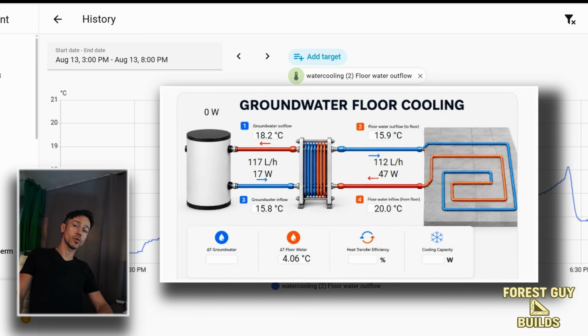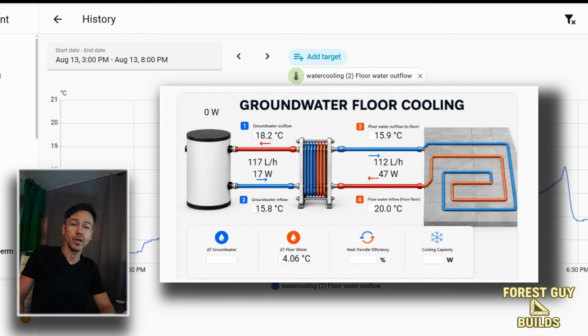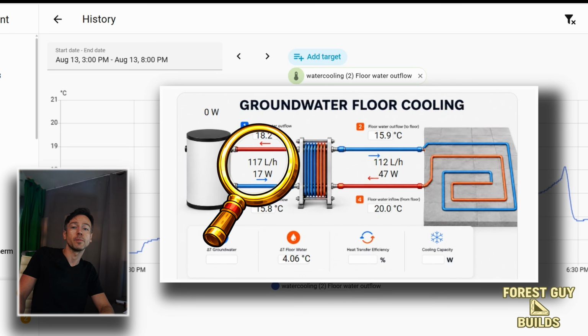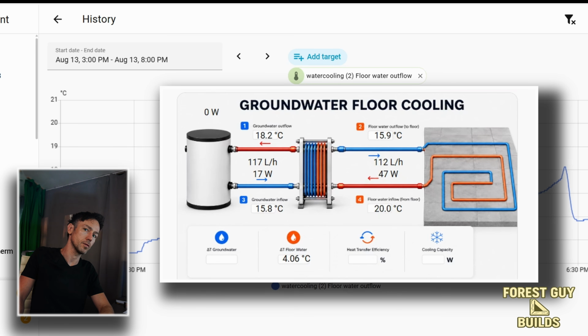Besides this, you saw the flow rates. Both the groundwater side and the floor circuits are running around 100 liters an hour, giving us a delta of around 5 degrees. As someone mentioned in the comments on a previous video, a delta of around 5 degrees is quite normal behavior for the type of heat exchanger I'm using here, so that lines up well having roughly the same flow on both sides. The bigger delta of around 7 degrees I had earlier was probably caused by providing much more cooling water to one side of the heat exchanger, resulting in that larger temperature difference.